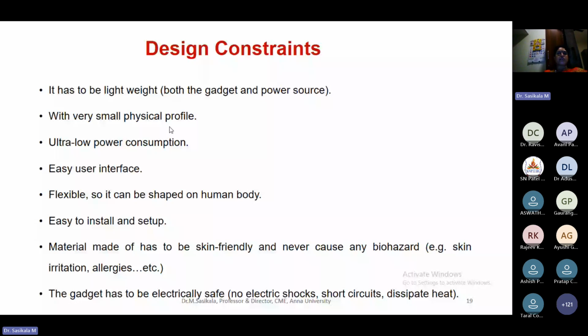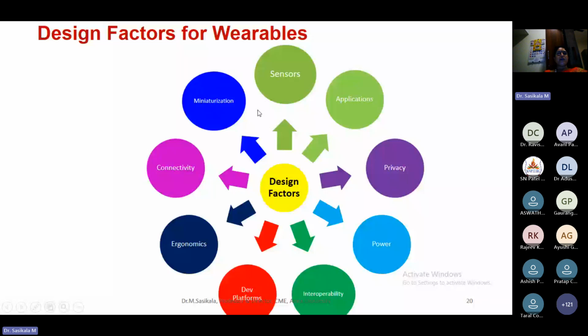So all the design factors are shown here. Whenever you design a wearable, depending upon the application, you first have to select the sensors - what kind of application am I going for? If I'm designing a fall detection system, I have to choose an IMU sensor, an inertial measurement unit. If I'm going to measure SpO2, I have to use an infrared LED and a photo detector to measure pulse rate and other parameters. So depending on what parameter you want - respiration rate or otherwise - you choose the sensors accordingly.